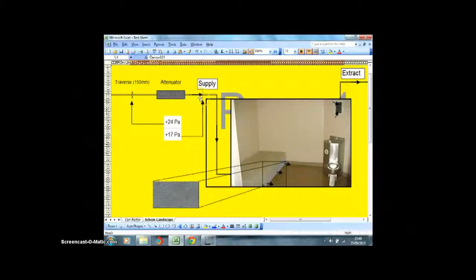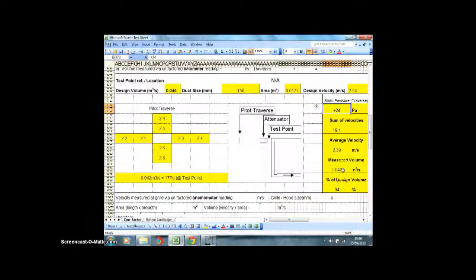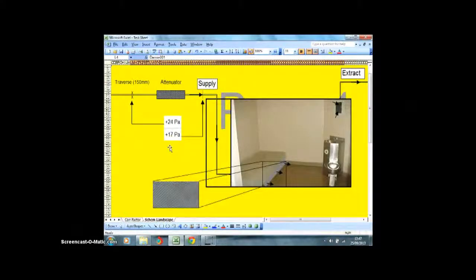So the initial scan basically proved that we're probably within 15 to 20% at each cell. So what I was able to do was to tie each cell into each other just on the pressure profiles that I was obtaining, and then do a correction factor at the end. So 17 pascals, as we proved here, equals 42 liters a second, or 0.042 meters cubed per second, relating to 17 pascals. At the end of the exercise, I was able to demonstrate to the consultant that it was viable. It did work. It did get accepted.